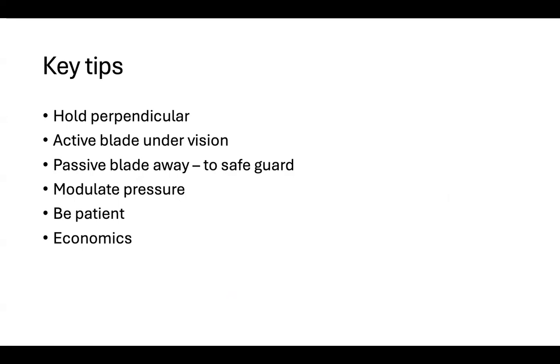And as I said earlier, always modulate the pressure, because it all depends on how much pressure you apply. If it is a tissue which is avascular and you want to cut soon, as few of you have observed in the surgeries I do, if it's an adhesiolysis, we just directly cut through. If it is a peritoneum, we directly cut through. If it's an avascular structure like the vault, we directly cut through. But if you feel it's a vascular structure, then apply moderate pressure and see that enough cooking or sealing of the tissue happens before you apply pressure to cut it. So you have to modulate the pressure. You have to be patient with your time. Only as a combination of these two will you be able to master the harmonic scalpel or the ultrasonic energy to use for your surgeries.